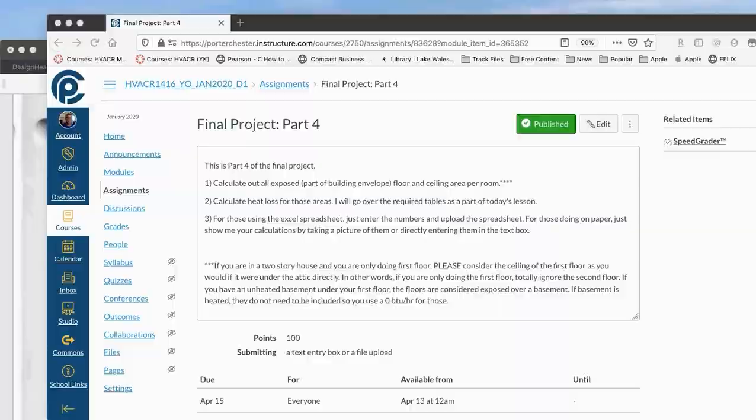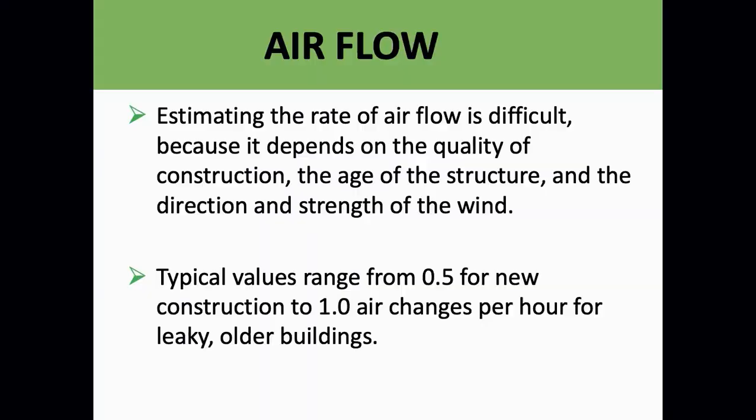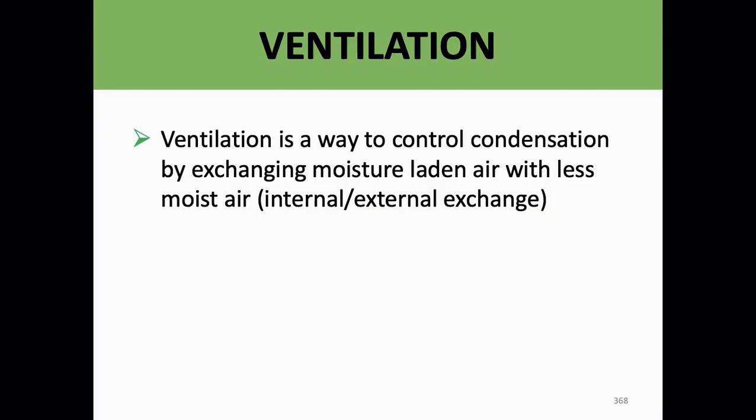Typical values of airflow range from 0.5 for new construction to 1.0 air changes per hour for older leaky buildings. This becomes very important with heating and cooling loads because of the humidity and the cold air that comes in. Ventilation is going to be part of your heat load. Ventilation is a way to control condensation by exchanging moisture-laden air with less moist air.